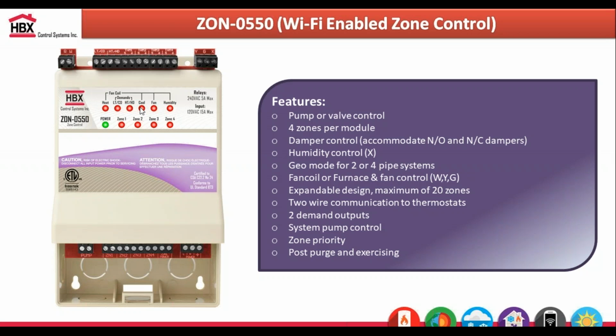All your first stage and your radiant is going to be at the bottom of the zone controller, and all your forced air elements are at the top. So we can control a fan coil, or we can send a heat call to your furnace, or a Y call to your air conditioning unit. We also have an X terminal to control humidity, so you can control a humidifier or dehumidifier all in the Zone 550. In terms of damper control, we can accommodate both types, normally open and normally closed. It's all built in terms of logic. Not necessarily why you would do this, but say you had 2 dampers that were normally open and 2 dampers normally closed. You could have those both on the same zone controller. You wouldn't need to separate them based on the damper type.